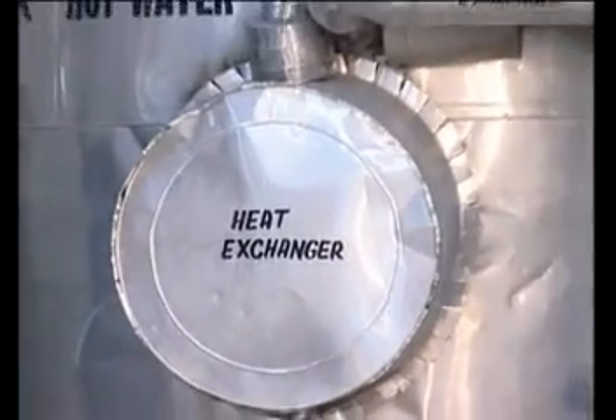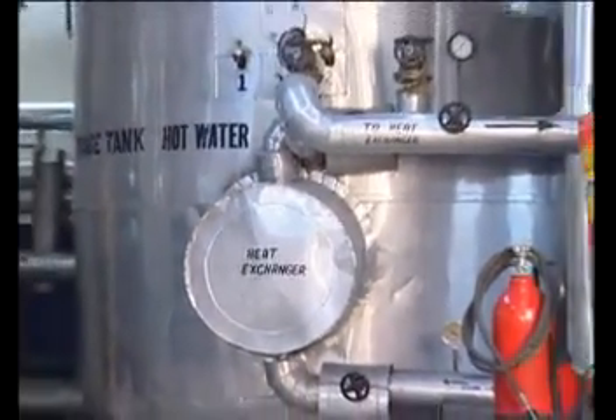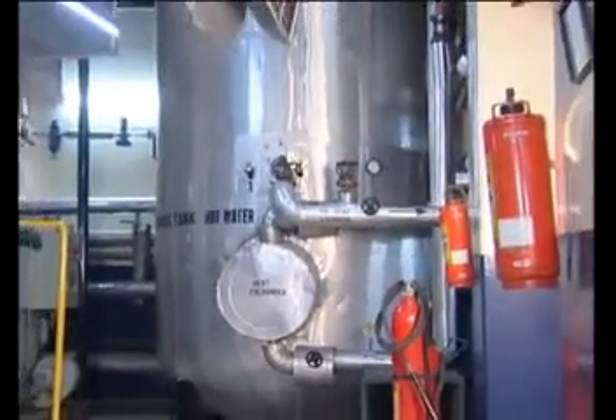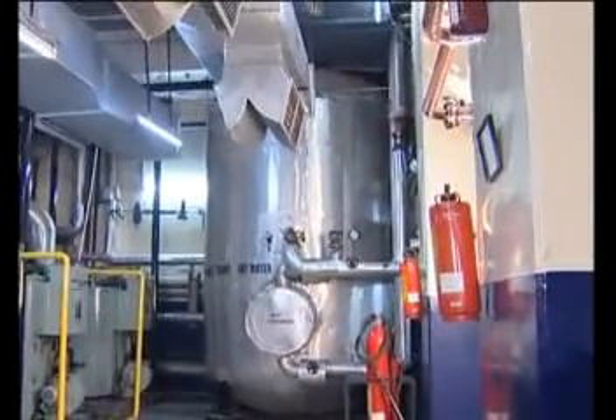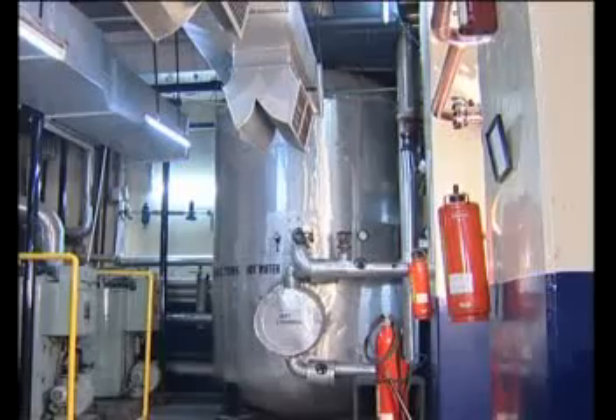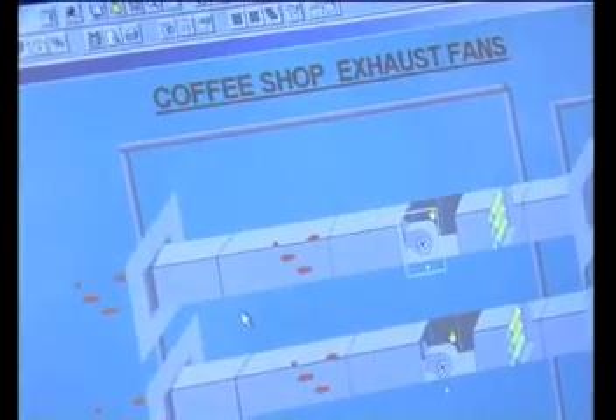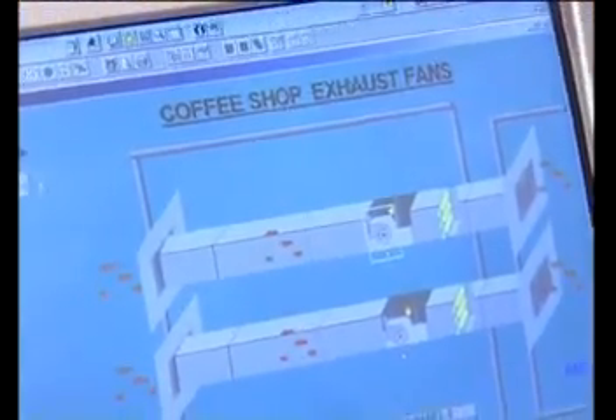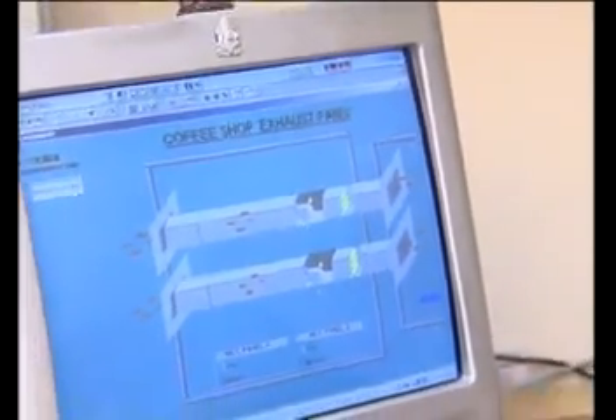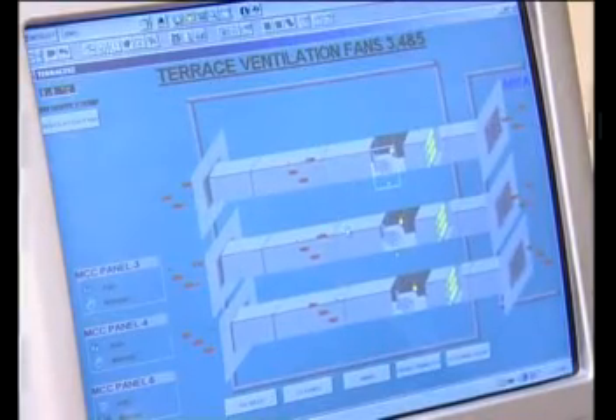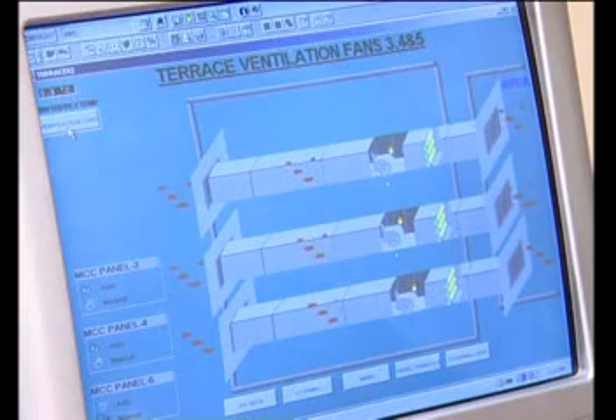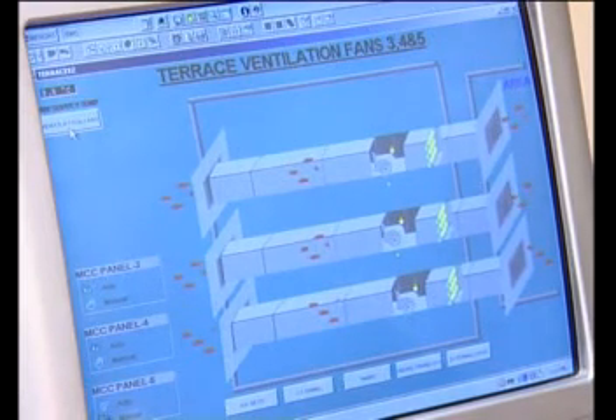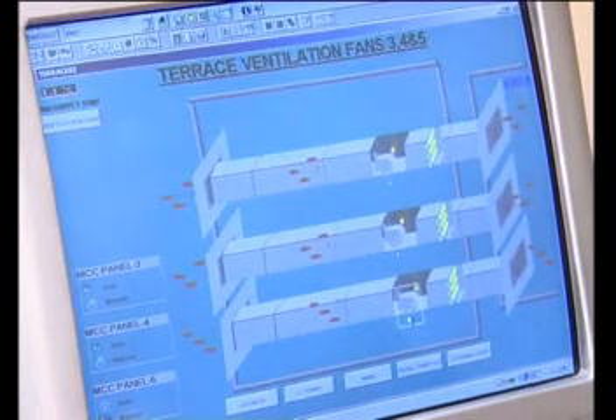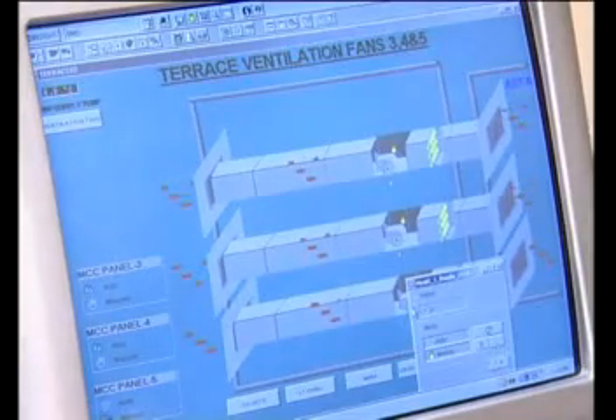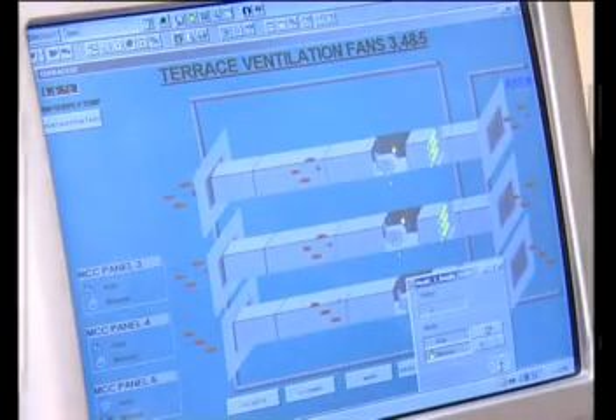The moment we started installing the heat exchangers for the condensate recovery, we found that we are saving to the tune of about 6 to 6.5 lakh rupees per annum. We started looking at the exhaust that was coming out of the running of the steam boilers. We found that after a year that we were saving more than 14 lakhs of rupees per annum, because we were not running our hot water boiler and saving the cost of gas.